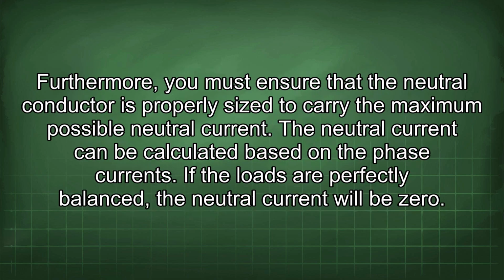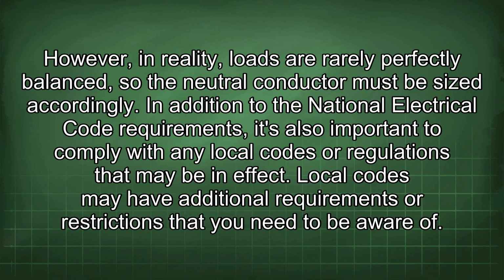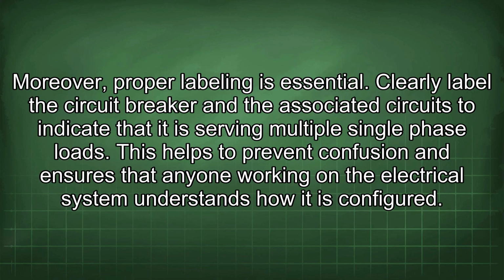Furthermore, you must ensure that a neutral conductor is properly sized to carry the maximum possible neutral current. A neutral current can be calculated based on the phase current. If the loads are perfectly balanced, the neutral current will be zero. However, in reality, loads are rarely perfectly balanced, so the neutral conductor must be sized accordingly. In addition to the National Electrical Code requirements, it's also important to comply with any local codes or regulations that may be in effect. Local codes may have additional requirements or restrictions that you need to be aware of. Moreover, proper labeling is essential. Clearly label the circuit breaker and the associated circuits to indicate that it is serving multiple single-phase loads. This helps to prevent confusion and ensures that anyone working on the electrical system understands how it is configured.